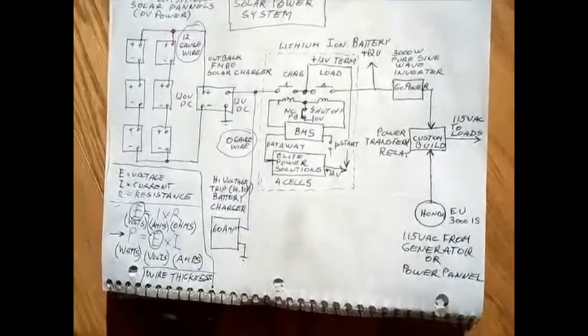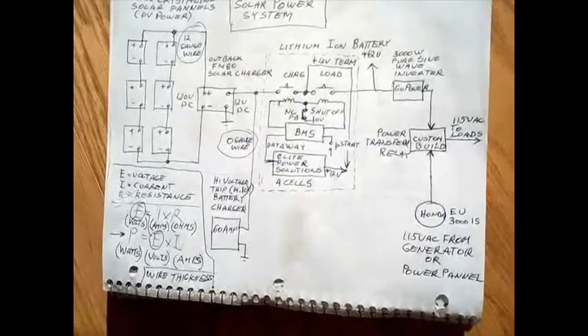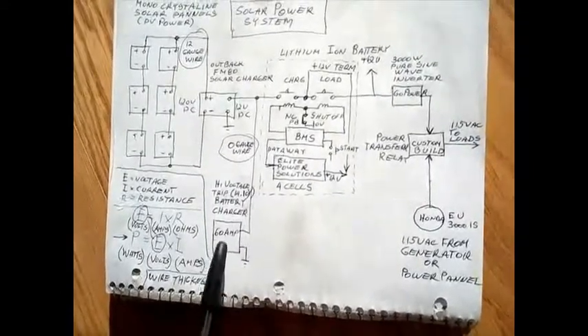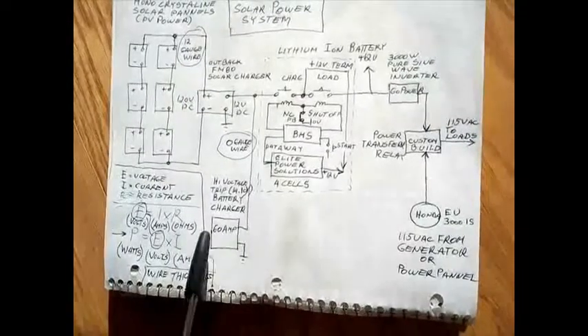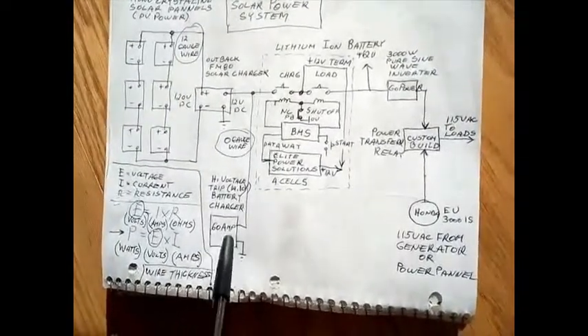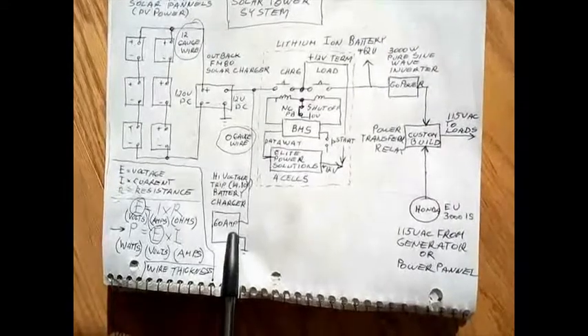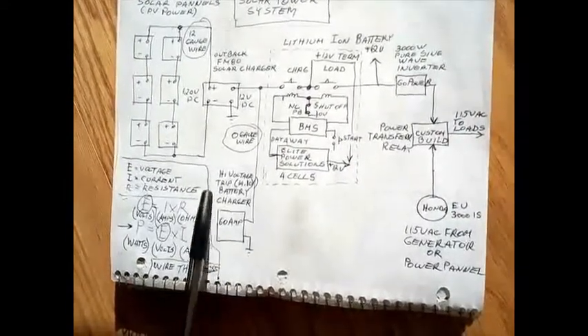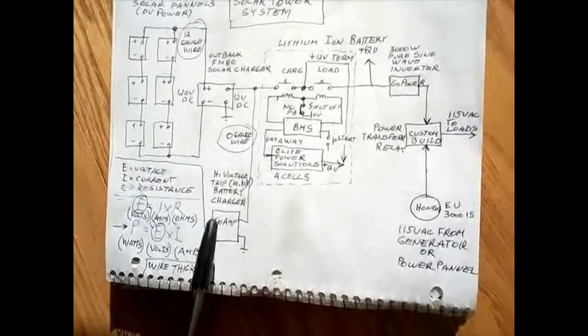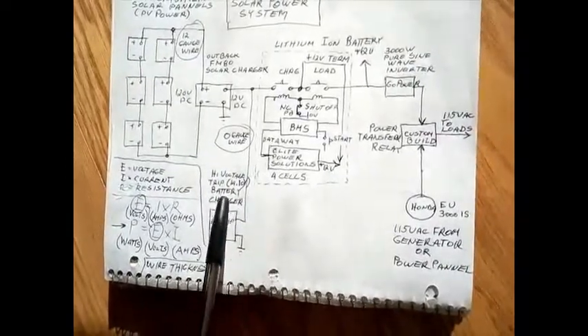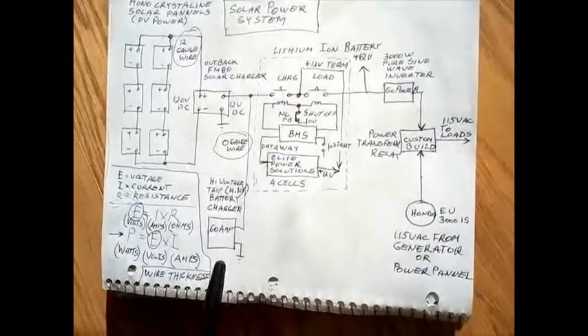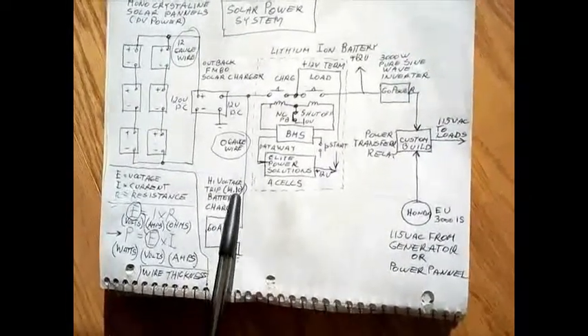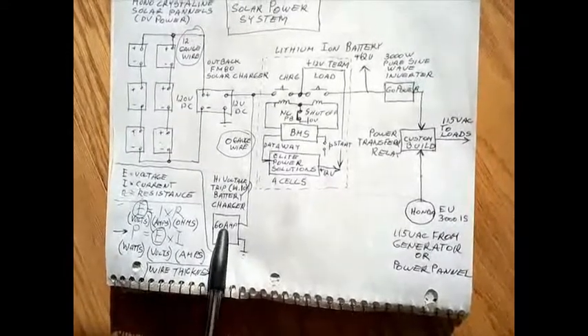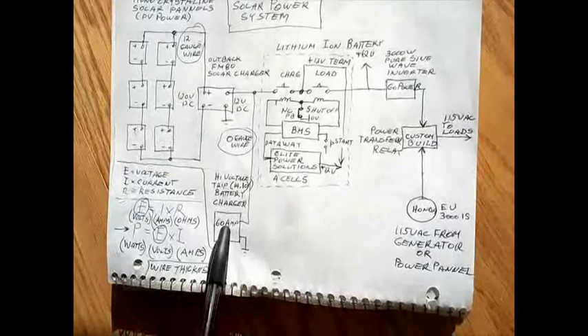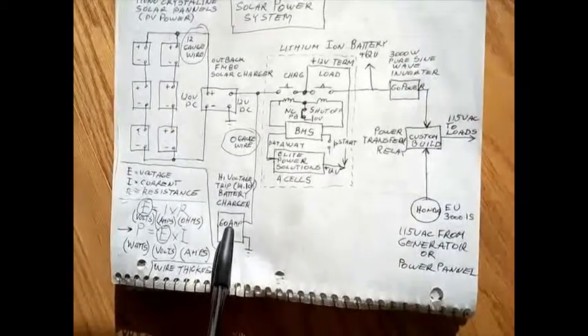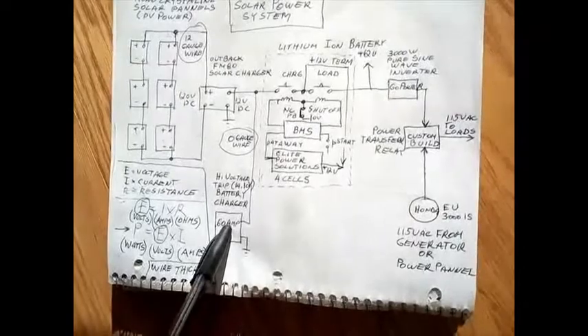One more thing we use when we have rainy days and the batteries go low, we use a 60 amp charger. Basically, any constant current at 60 amps will work with a lithium-ion battery, provided that there's a high voltage trip. And in this case, it's set to 14.10 volts. Once it reaches 14.10 volts, the 60 amp charger is taken off the batteries. We don't want the voltage to go any higher than that. Okay.